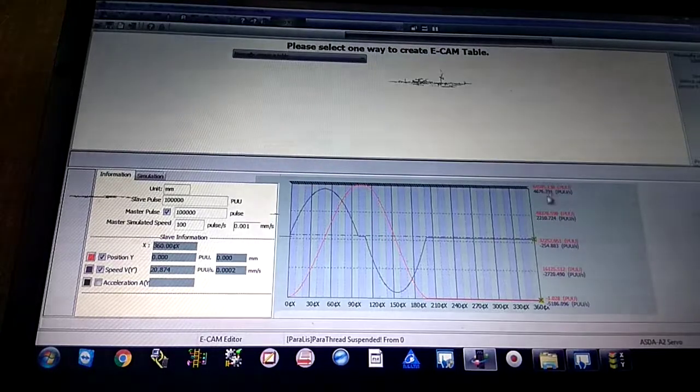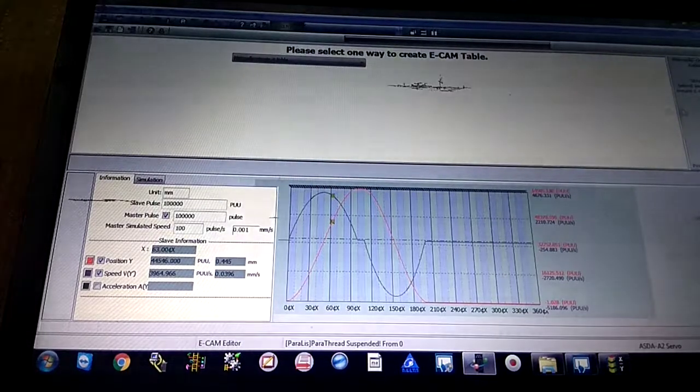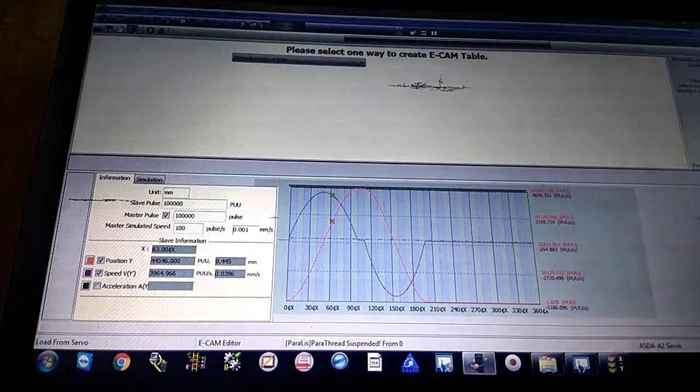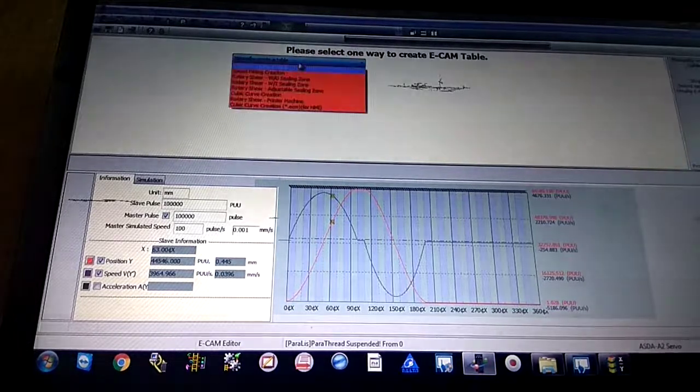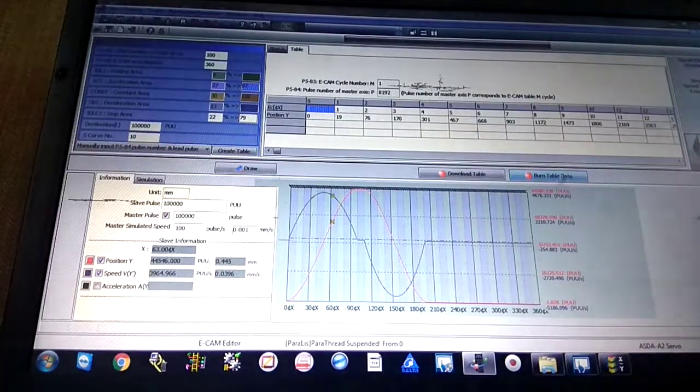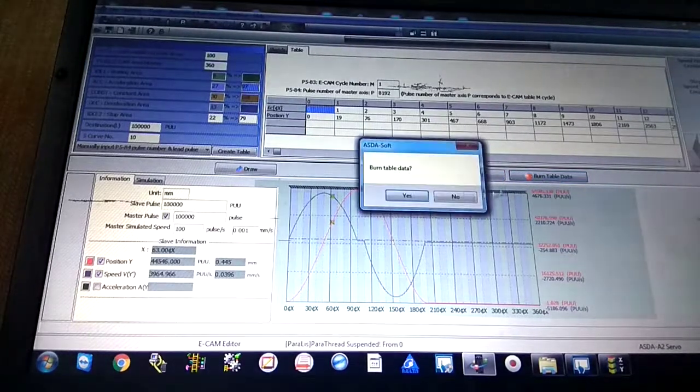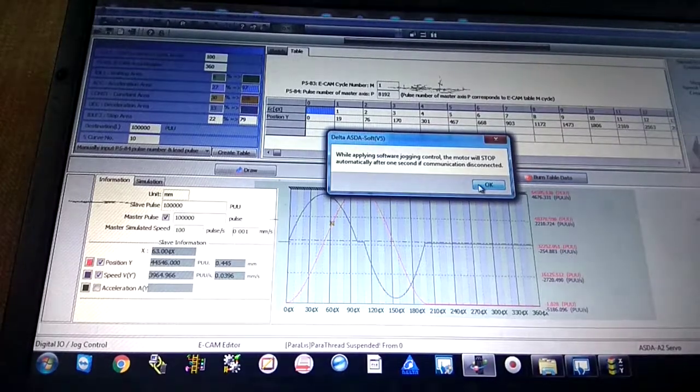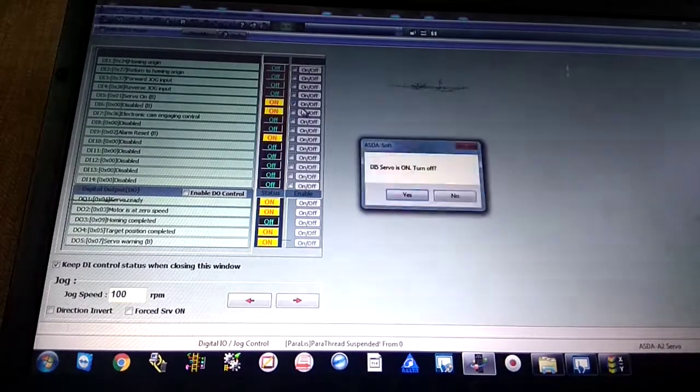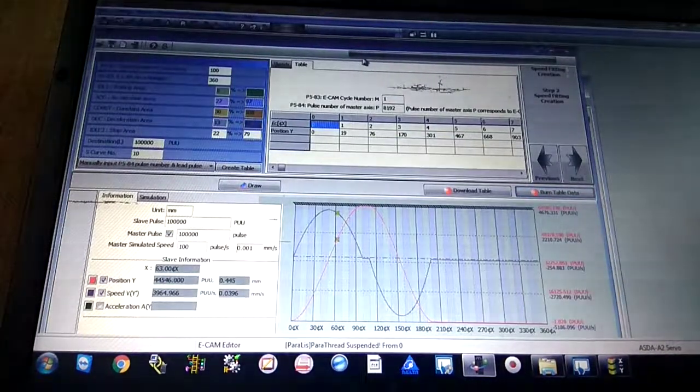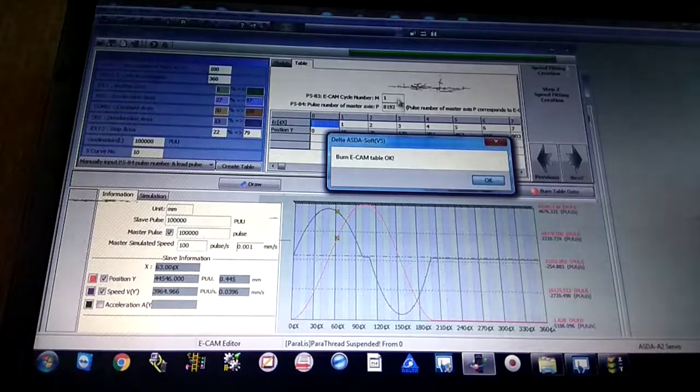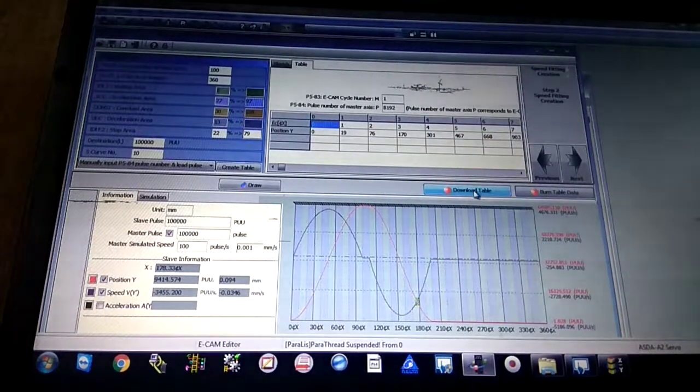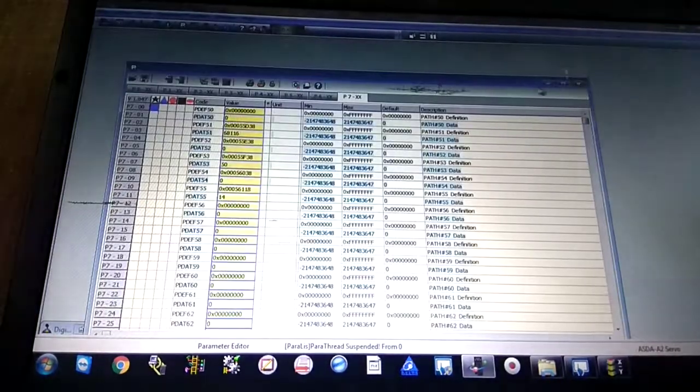Let me tell you how to download this E-cam on servo drive. This is very easy. Just go to the next button. You can see this is burn table data, download table. Go to burn table, yes. Because I already downloaded the program and the servo is on, I have to put servo off first, then download the program. Burn table. See, the program is burning. Now your E-cam is burned on your servo drive. Download table, okay, that is fine.